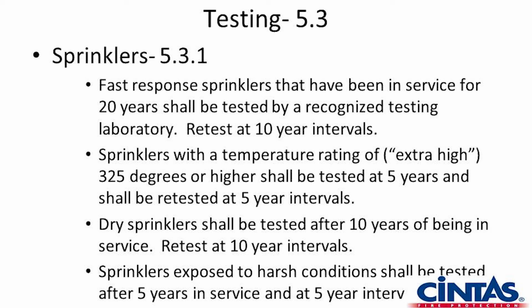NFPA has put out a report that says that 50% of dry sprinklers that are sent into UL for testing fail their inspection. So unless you have many dry sprinklers, if we're talking about 6 to 8 within the facility, we're generally going to recommend you replace all 6 or 8 sprinklers.